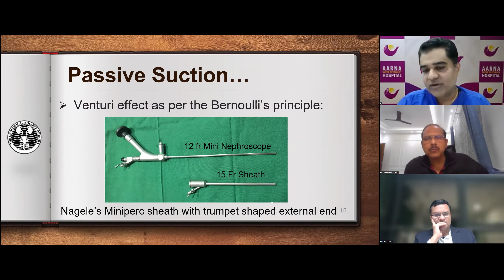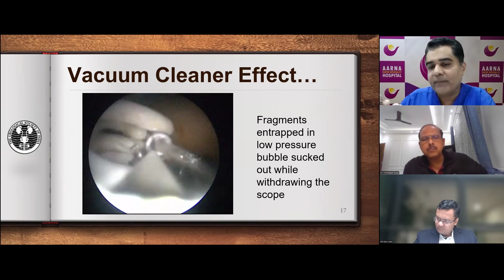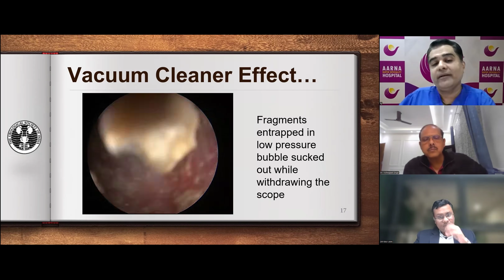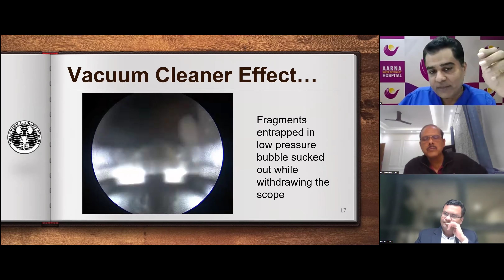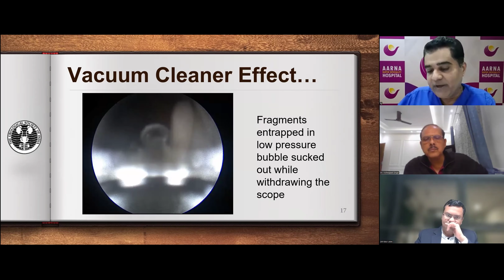The idea was to get a rounded shape at the internal end and a trumpet shape at the external end. Because of these shapes, the fragments used to get entrapped in a low pressure bubble, which was created because of the differential pressure gradient. And when we withdrew the scope, with that bubble, all the fragments could be sucked out. And when we get out of the trumpet end, we can drop down those fragments and achieve the clearance. So this was the vacuum cleaner effect or Nagele's effect, which helped us in mini-PCNL before the active suction came into role.